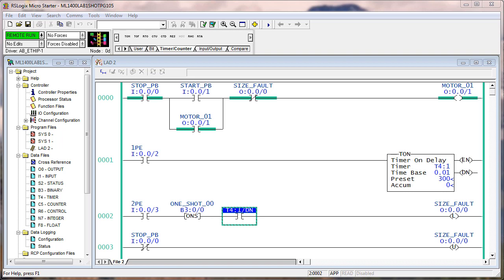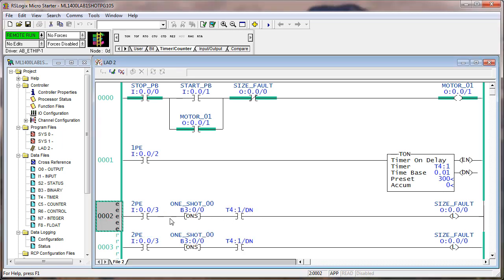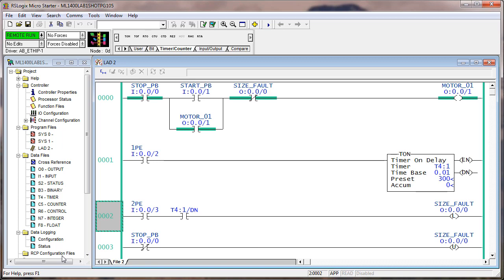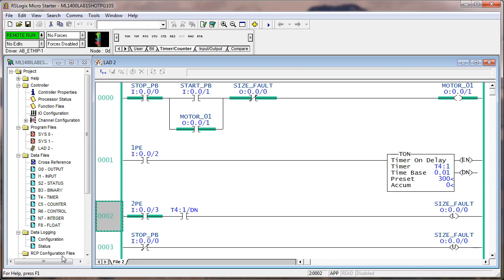You could actually take out the one-shot and this would still have some function. So I'm going to put this in edit mode and cut that out so I can easily paste it back in. The conveyor is running — we're going to block 1PE, but if 1PE clears before 2PE hits, not a problem. Now where we lose it is if 2PE is already blocked erroneously and then we block 1PE — as long as we clear 1PE before the timer times out, we're fine. So basically if we take out the one-shot, we've eliminated the need for 2PE, but I prefer to keep 2PE with the one-shot and the timer.